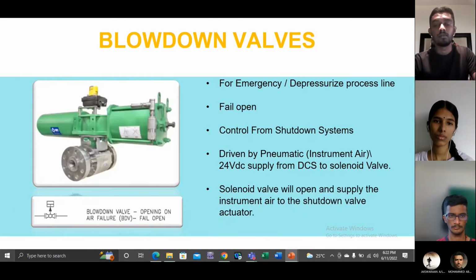So this is another type of valve, blowdown valves. It is also for emergency, to depressurize the process line, in case of fail open, controlled from the shutdown system, driven by pneumatic. This is also using air and a 24 volt DC supply from DCS to the solenoid valve. The solenoid valve will open and supply the instrument air to the shutdown valve actuator.